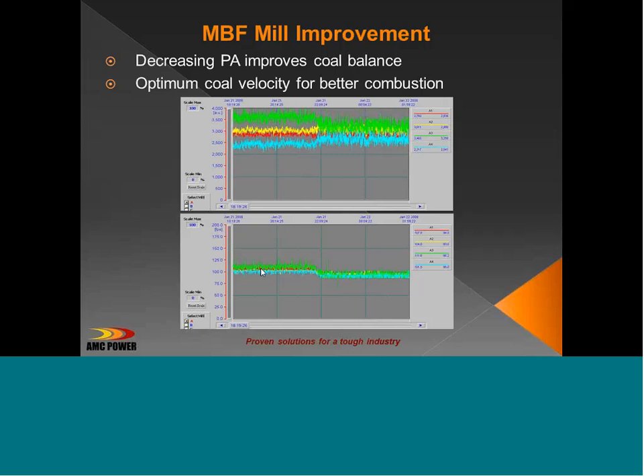Now, primary air curves and how much primary air you need for what fuel type can be debated back and forth, but I can assure you that 100 feet per second is not desirable. And in a case like this, you're going to blow this coal right through the flame. You're going to have high superheat, reheat temperatures. You're going to see a cloudy furnace. It's not going to be very pretty, and that's exactly what this particular power plant had.